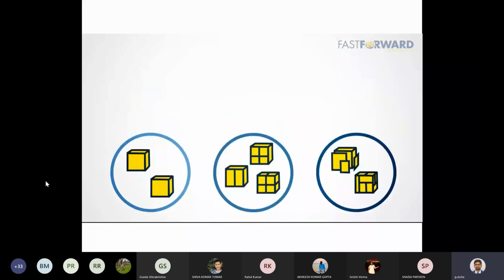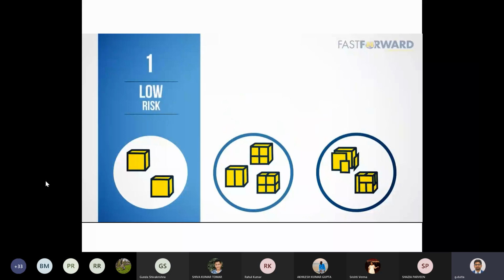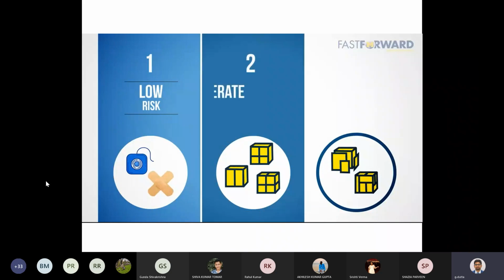Class 1 devices pose the least risk to the patient and frequently only require a registration as manufacturer of record with the FDA. Think elastic bandages or dental floss. Class 2 devices pose a moderate amount of risk and most often require a pre-market clearance from the FDA before they are sold. Class 2 devices are the most common and include things like pregnancy tests, infusion pumps, and monitoring devices.